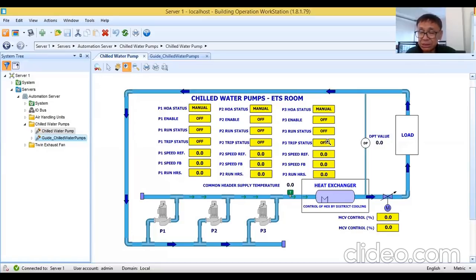So you still have one spare, but it's not good having only one spare because maybe the consultant will not allow it. Okay, so at least select one IO module with 16 universal input, then one analog output combination with universal input, analog output with 4 analog output, then 8 universal input. So total 16 plus 8, you have 24. So that is more than enough to cover the spare points. So the consultant will not complain if you do not provide the spare points.